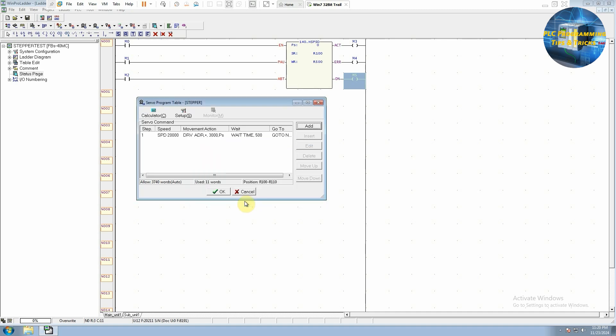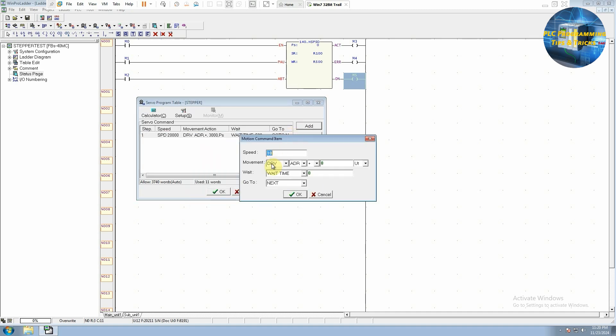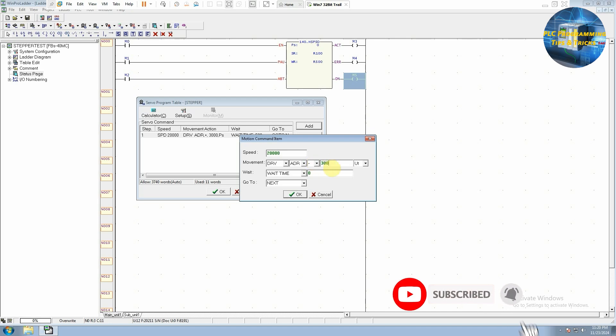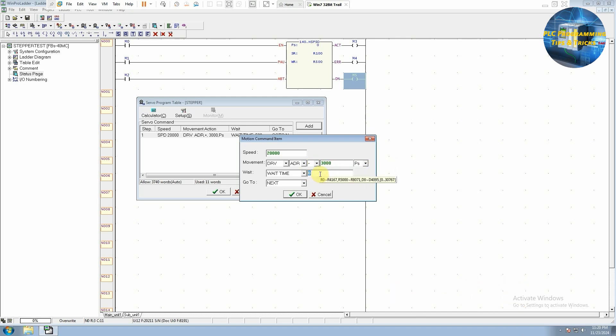To add the next positioning step, we click Add and keep all settings the same as the previous step, except direction — we select the negative sign, meaning the motor will run in reverse. We enter a 1-second delay in the wait time and select End from the Go To menu, so the function stops execution after this step.